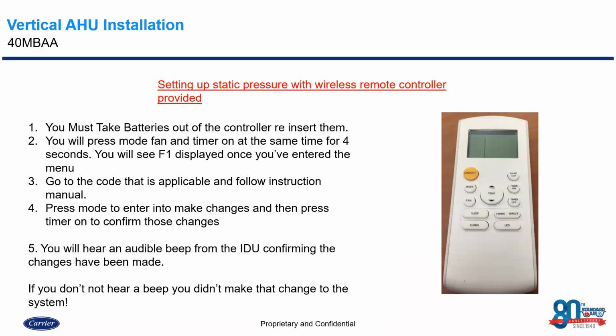So now we've got everything piped, we've got everything wired, dip switches are set, everything's set up. So we have one last thing that we have to do, and I kind of alluded to this in previous slides: we have to set up the static pressure, because it doesn't come from the factory with that maximum static pressure of 0.8 inches. Okay, so there's two ways to do this.